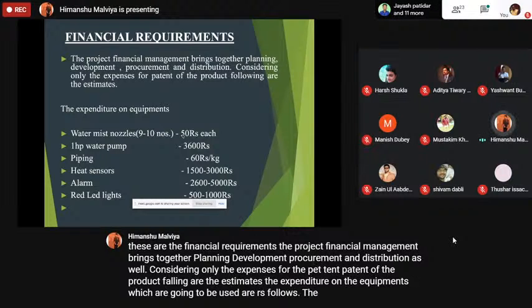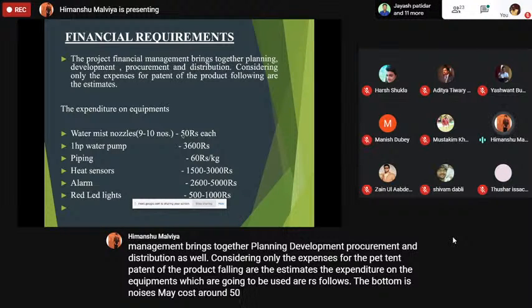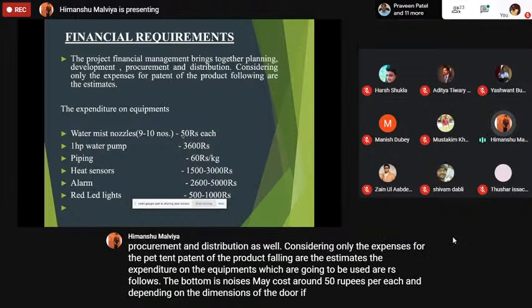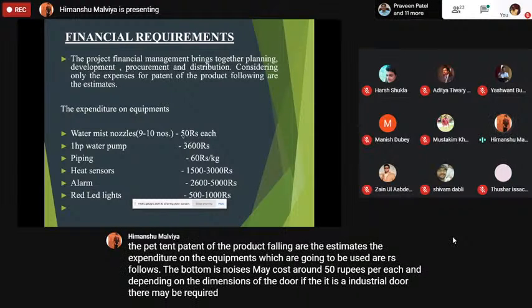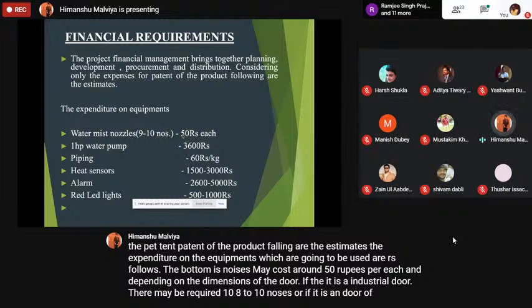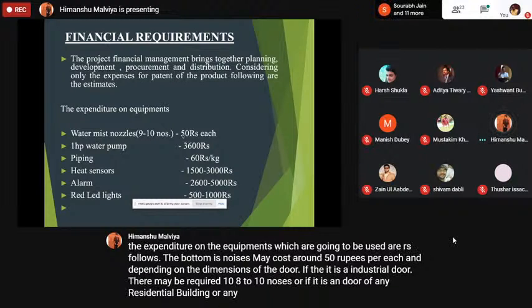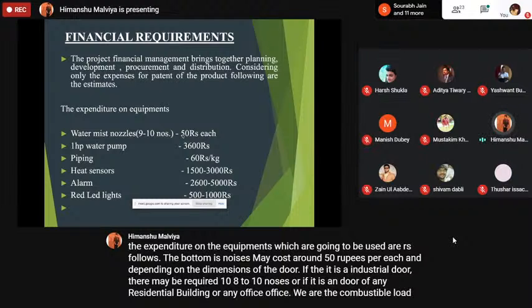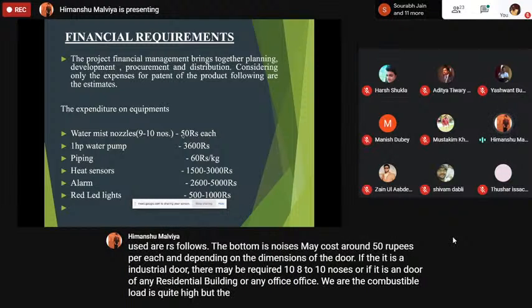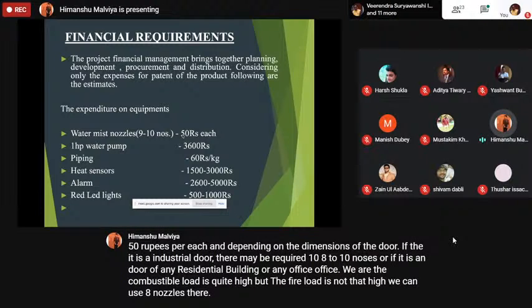The water mist nozzles may cost around 50 rupees each, and depending on the dimensions of the door, if it is an industrial door, 8 to 10 nozzles may be required. For a door of any residential building or office where the combustible load is quite high but the fire load is not that high, we can use 8 nozzles. These are the financial requirements.